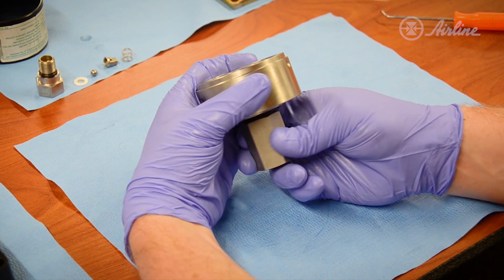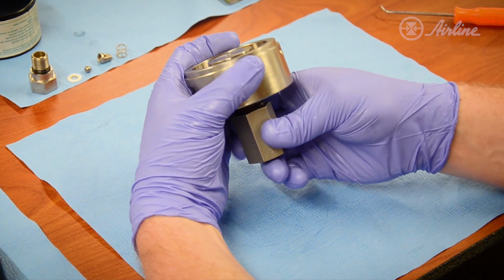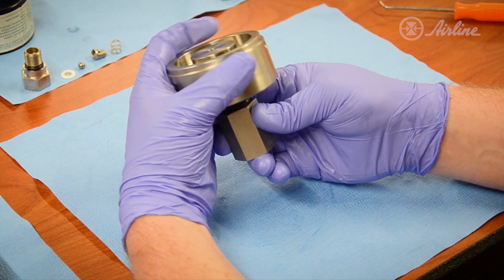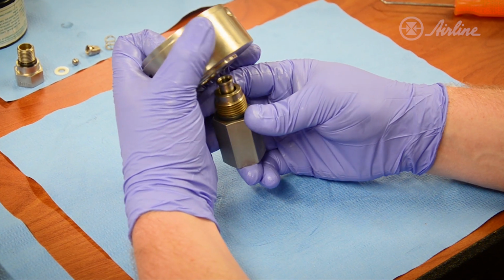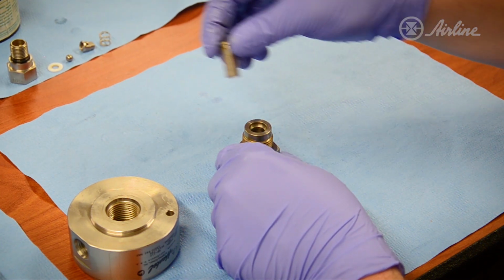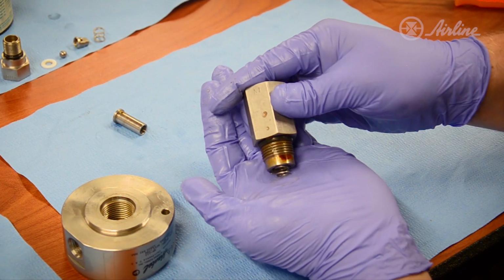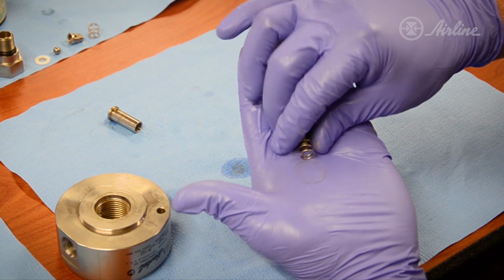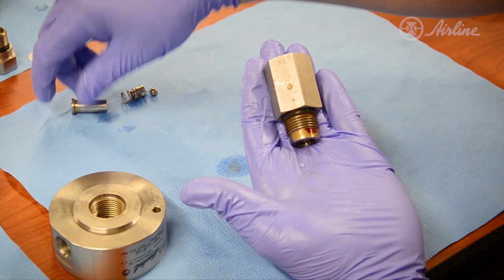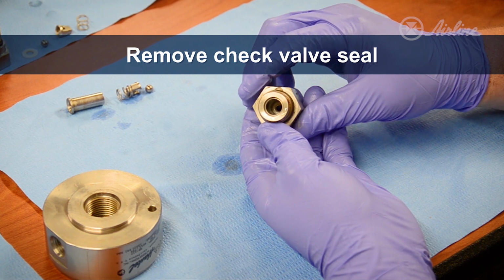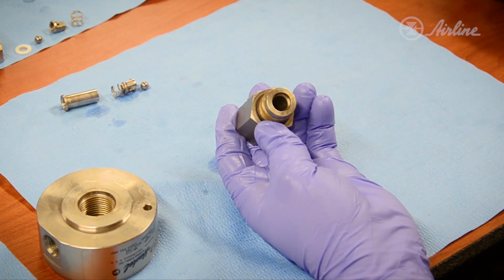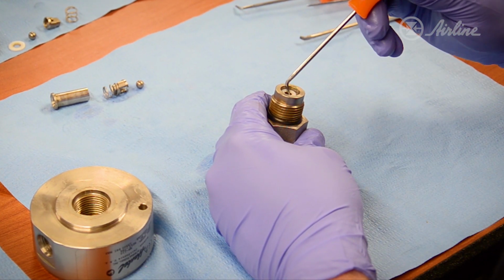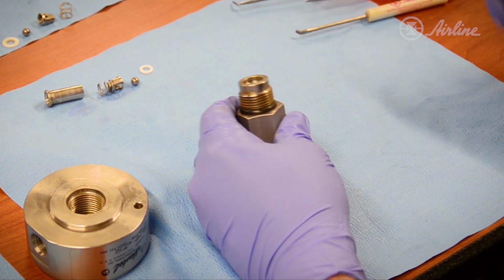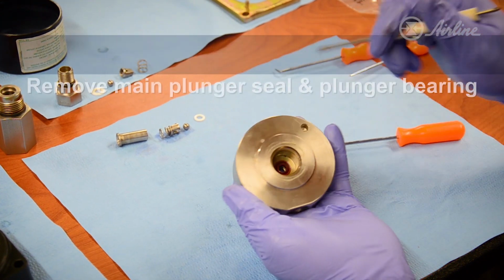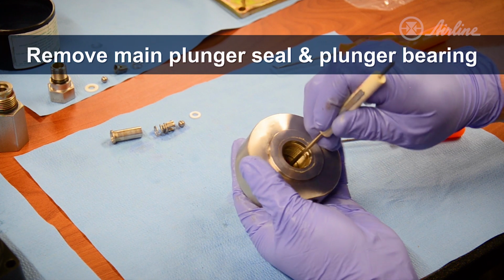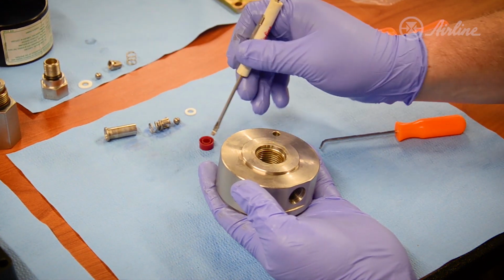Again, we need to take care when we're taking these apart to keep all of the internal components in the correct order. If they do get mixed up, you can reference the drawing you've printed out for their proper reassembly. So we have the standoff tube and then the check valve components. And also in the base of this fitting is where the other check valve seal is that we need to replace. And set it aside. The last two components to remove from the pump head are the main plunger seal and the plunger bearing. These can be picked out after the inlet check valve has been removed.